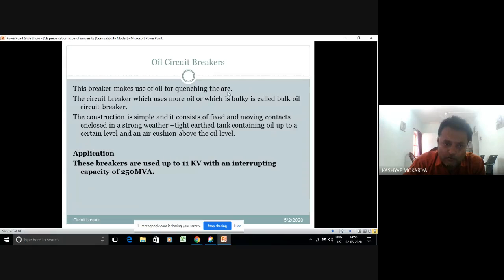This is a moving contact of the oil circuit breaker. This breaker makes use of oil for quenching. It has two types: a minimum oil circuit breaker and a bulk oil circuit breaker. The circuit breaker which uses more oil, which is bulky, is called a bulk oil circuit breaker. Remember, oil is used as an arc interruption medium, and oil is also used as an insulator here. In a minimum oil circuit breaker, the majority of the insulation is done by the porcelain unit, so you have very little oil there. That's why it was named MOCB. For BOCB, the major part is covered with transformer oil.